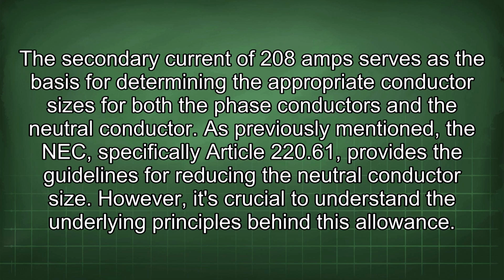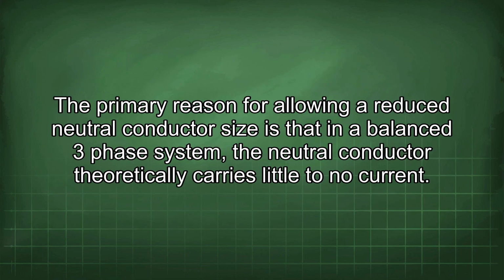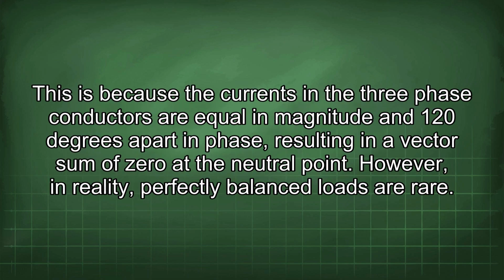However, it's crucial to understand the underlying principles behind this allowance. The primary reason for allowing a reduced neutral conductor size is that in a balanced three-phase system, the neutral conductor theoretically carries little to no current. This is because the currents in the three-phase conductors are equal in magnitude and 120 degrees apart in phase, resulting in a vector sum of 0 at the neutral point.